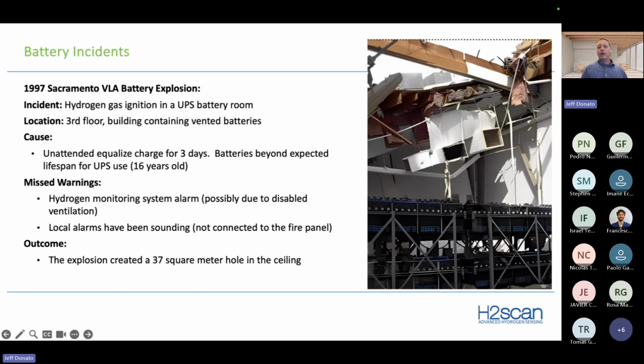So we do have a risk, and some of the risk is not just because batteries emit hydrogen. Some of the risk is how our facilities are constructed, how we have our detection systems put together, and what our mitigation plan is if something were to go wrong with any system, and that includes a mechanical failure. In this case, this was not a problem with the battery. The room was constructed properly, but inadvertently a maintenance person or a facilities person decided to turn off the ventilation system, and therefore created an accumulation of hydrogen.